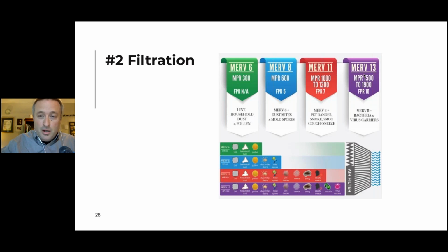It takes a MERV 13 or higher. This is still not perfect. This will knock out about 75% of the viral particles that are in that ballpark, the 1 to 3 micron range. Doesn't necessarily do a great job under 1 micron. Sometimes it does. So if you really want to do a good job, you need to move to like a MERV 16. The problem is every time you go up here, you create a bunch of extra back pressure. And if you aren't careful, you can kill the motor in your furnace or heat pump in a couple of years. I've seen them fail in 18 to 24 months when somebody put the wrong filter in. So that's a critical thing.